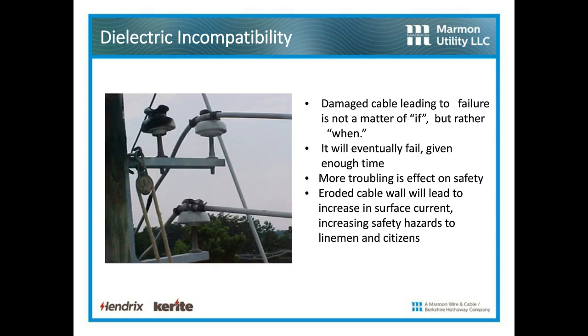And there's what that failure looks like. You can see the cable on the top insulator is blown. If you take a look at the right insulator, you can see that there's tracking and cracking there due to that partial discharge. So the damaged cable leading to a failure is not a matter of if, but simply a matter of when. It will eventually fail, give it enough time. More troubling in my mind is the effect on safety. Again, as I start creating partial discharge through dielectric incompatibility, I'm eroding that insulation. I'm decreasing its insulation characteristics. I'm increasing the amount of current that's on the surface, and that's going to pose a safety issue for linemen and citizens should they come in contact.